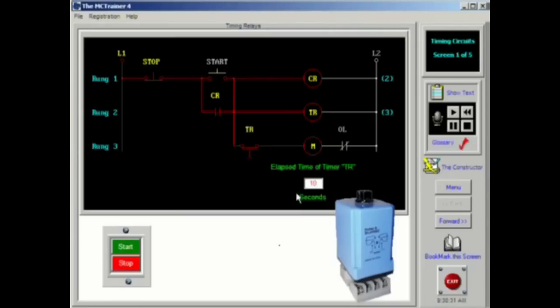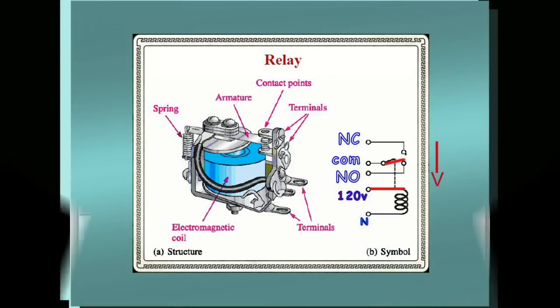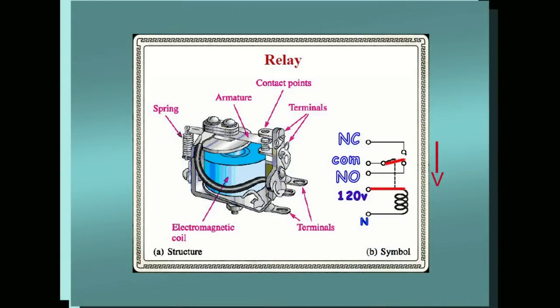The off delay is designed to operate its contacts in response to the closure of an initiating switch. Closing the switch will cause its normally open contacts to close instantly, and its normally closed contacts will open instantly. As long as the initiating switch remains closed, the contacts will remain in their active state.